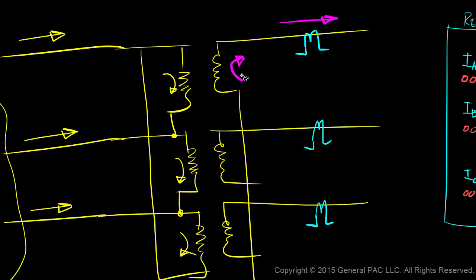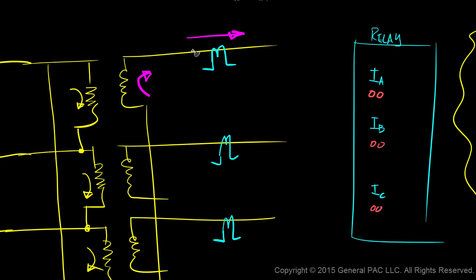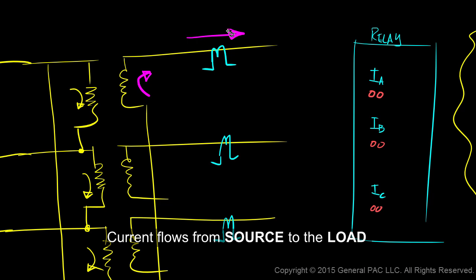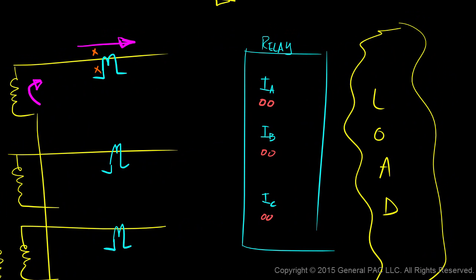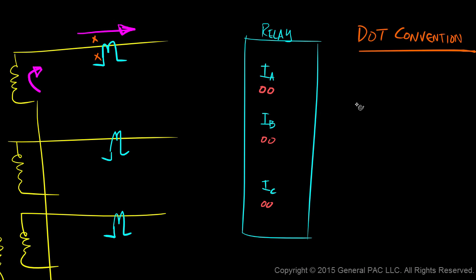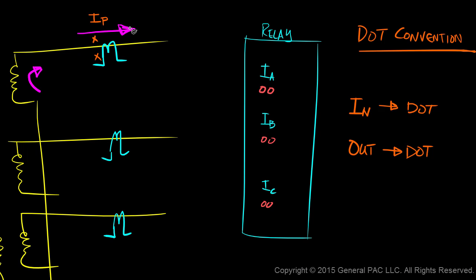Let's zoom back in to our CT connected to phase A. Suppose that the current in our steady state flows in this particular direction. In terms of polarity marks, we typically see them in two places: one on the line side, and the other on the CT side. To interpret this, we follow what's called a dot convention. The dot convention has two rules: current in to the dot, and current out of the dot. If primary current flows into the dot on the primary side, then the secondary current must flow out of the dot on the secondary side.